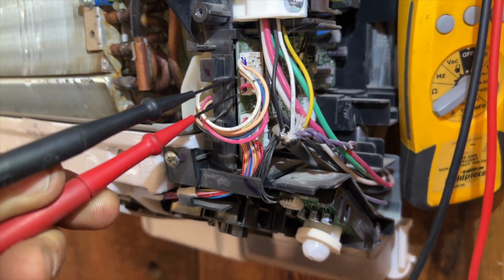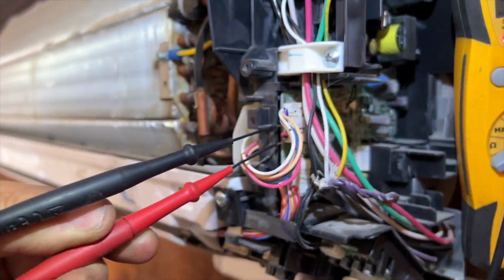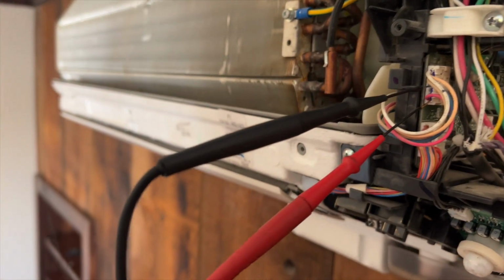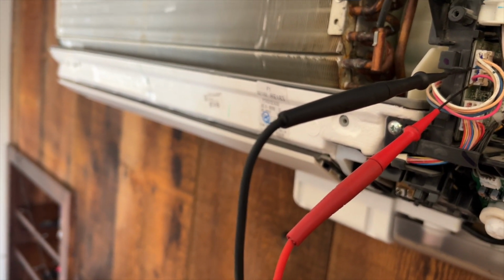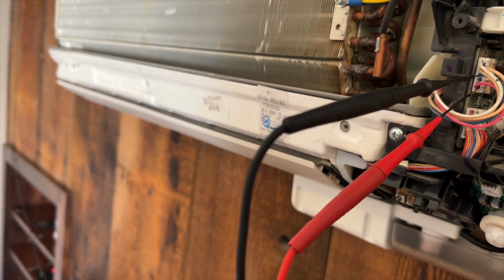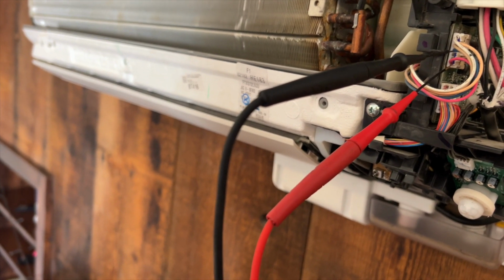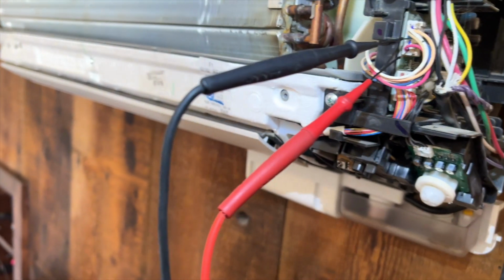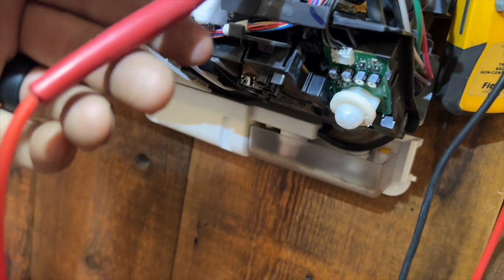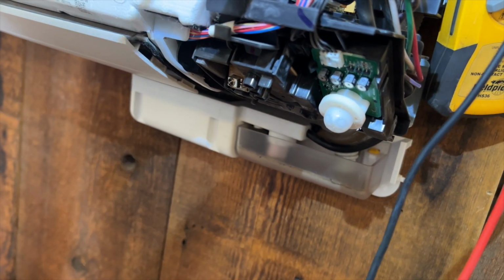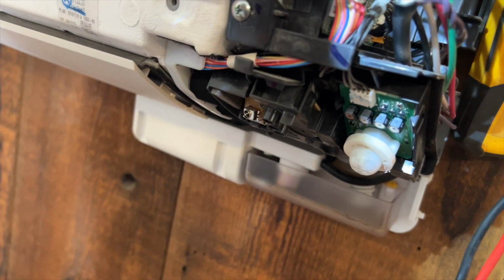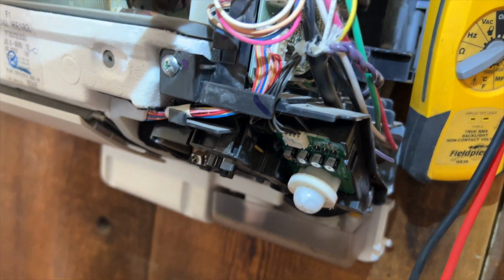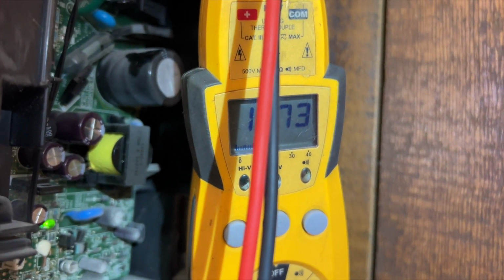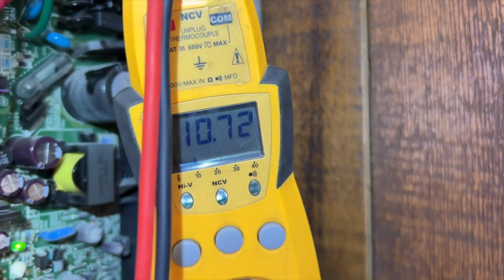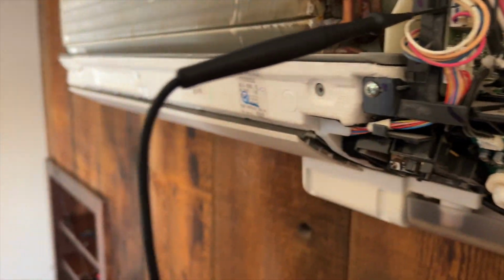So this is where the micro leads come in handy. Okay, so we're within range. Okay, so the next thing we want to do is we want to check pin 3 and 4, and that should be 15 volts DC, so that's going to be the one right above this one here. Okay, so that's 10 volts, so it's a little bit low.